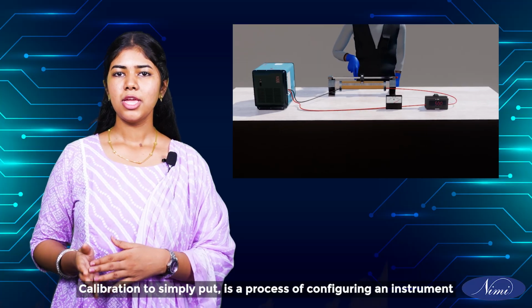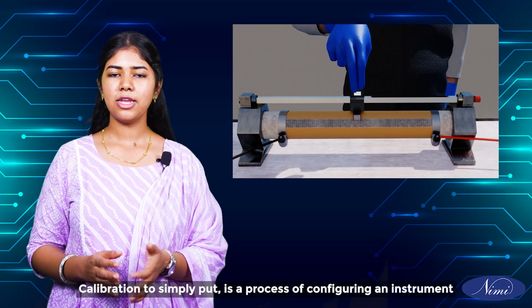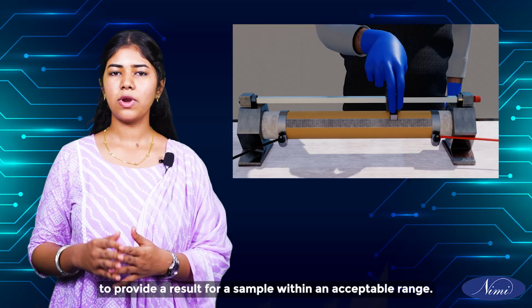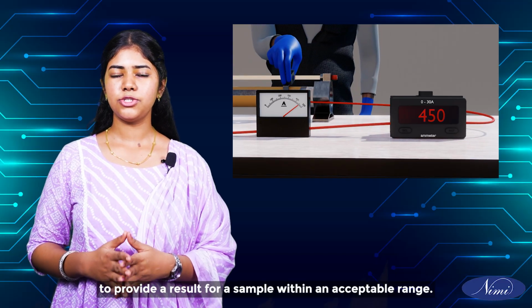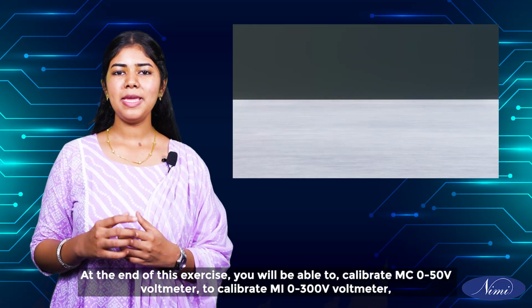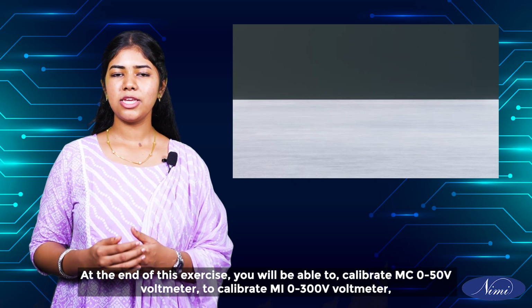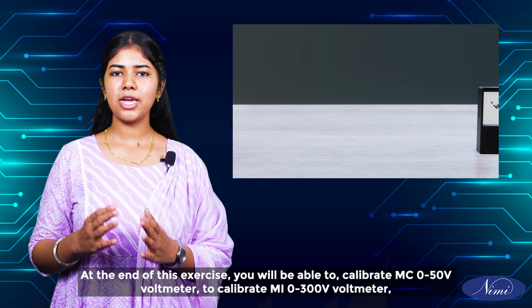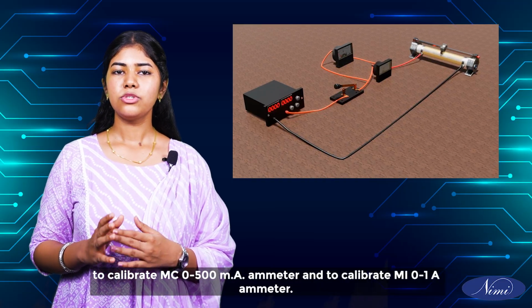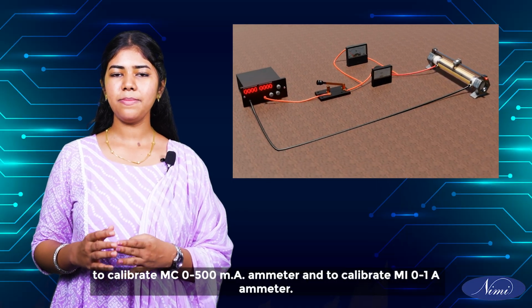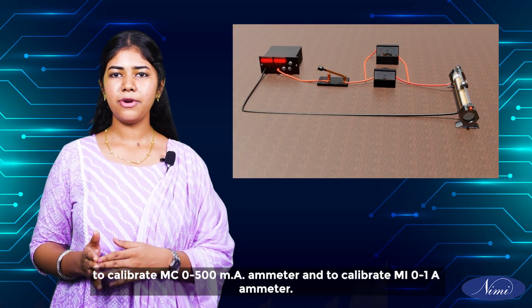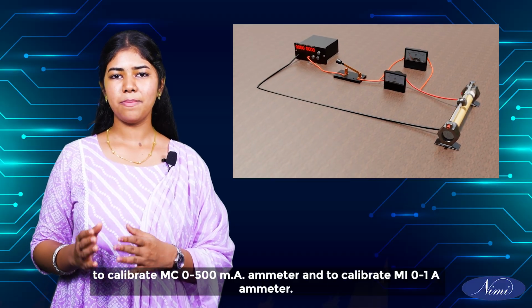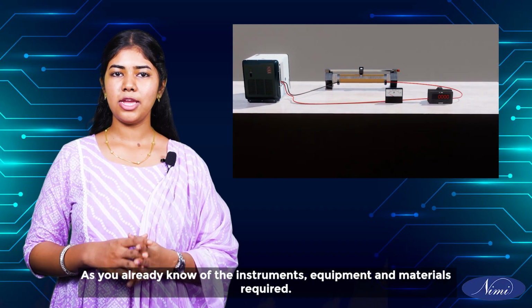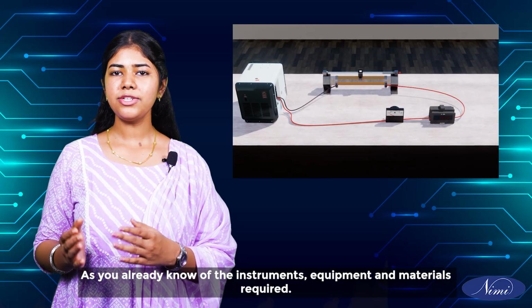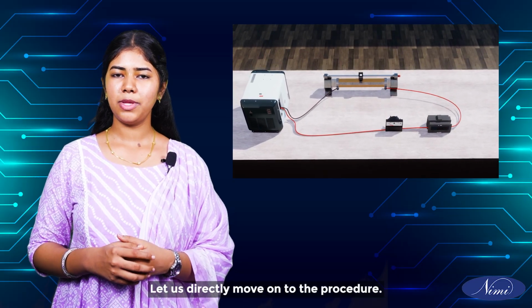Calibration, to simply put, is a process of configuring an instrument to provide a result for a sample within an acceptable range. At the end of this exercise, you will be able to calibrate MC 0 to 50 volts voltmeter, to calibrate MI 0 to 300 volts voltmeter, to calibrate MC 0 to 500 milliamperes ammeter, and to calibrate MI 0 to 1 ampere ammeter. As you already know of the instruments, equipment and materials required, let us directly move on to the procedure.